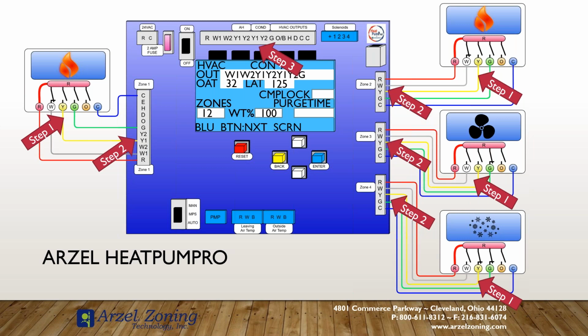And while we don't necessarily have to go to each individual device to test it with our meter, we can turn everything on how we want it to work. And then we can go to the Arzel panel. The Heat Pump Pro has the screens that walk you right through your diagnostic. Tells you exactly what thermostats are calling, tells you exactly what's being outputted for. So if we start there, we get a high overview of what's happening. And then we can know that this, and this are working. But if we don't see it happening the way that we think it should, or the way that it's supposed to be, now we can focus our diagnosis there.